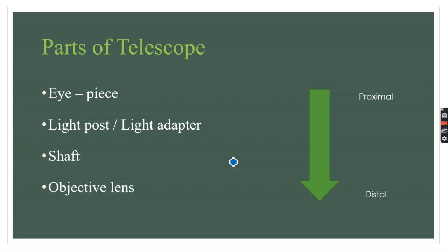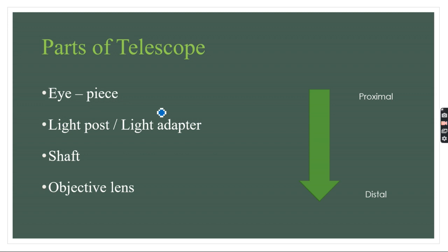There are four important parts of the telescope, going from the proximal end to the distal end. The distal end is the portion that goes inside the abdomen or thoracic cavity, while the proximal end lies outside. Traveling from proximal to distal: the first part is the eyepiece, then just distal to that is the light post or light adapter, followed by the shaft — a long rod-like structure — and finally at the distal end, inside the shaft, there are various objective lenses.